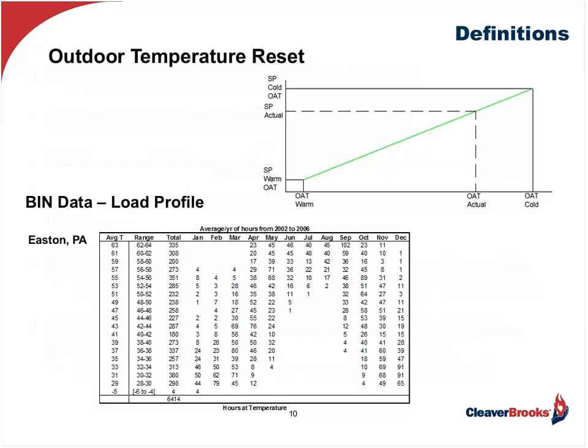Now, outdoor air temperature reset, as you can see here, is resetting the hot water temperature set point based on outdoor air. In this case, this is for Easton, PA, there's a design temperature of about -5. I might have 160-degree supply water temperature. All my terminal units have been picked for that temperature. However, as you can see in the bin temperature here, we don't list all the temperatures, but the vast majority, more than 6,400 hours, are well above 29 degrees Fahrenheit. Most of the time, I don't need full output from my heating devices. So I can put in a control sequence to reduce my supply water temperature as that outdoor air temperature increases. And it'll vary from maybe a high of 160 down to a low of 130.